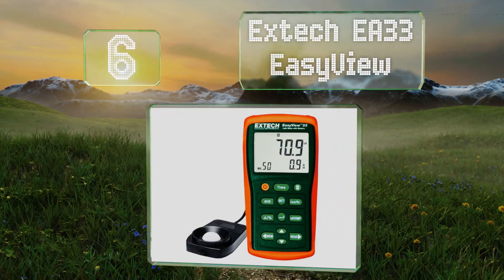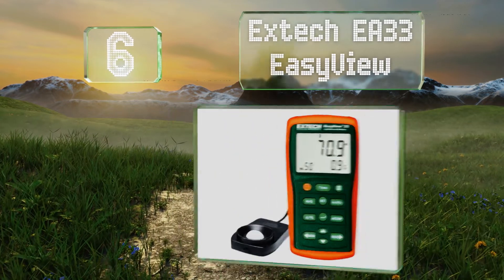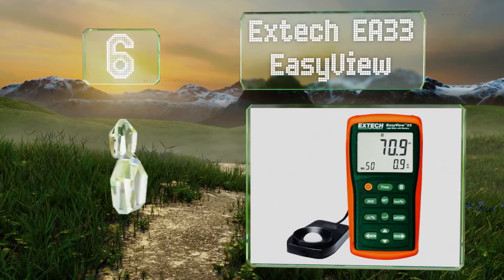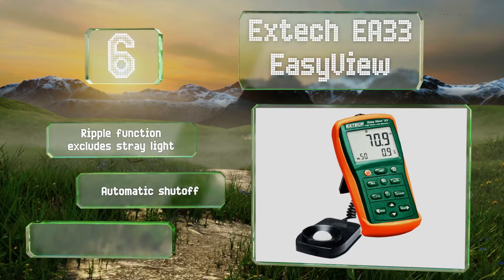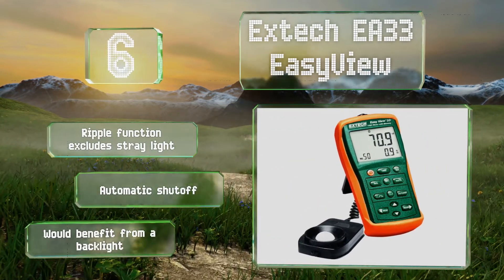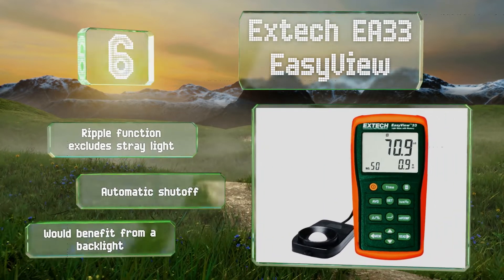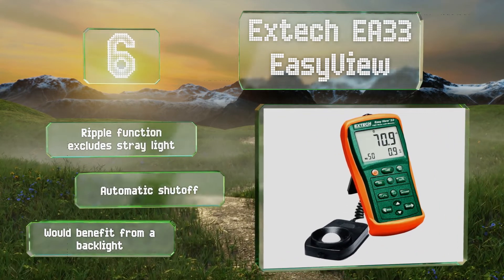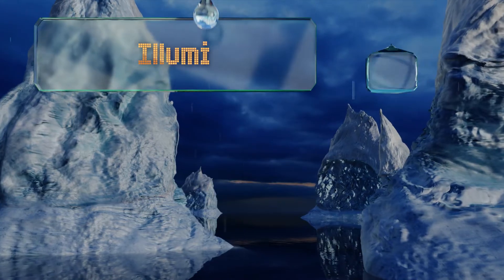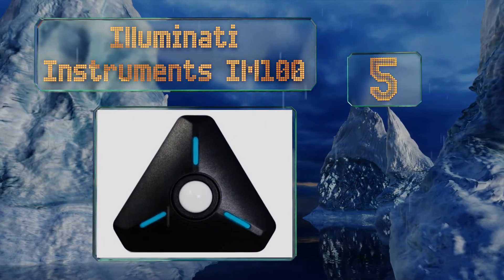Moving up our list to number six, the compact Extech EA33 Easy View features a large LCD screen and a wide measurement span reaching 99,990 foot-candles in five ranges. It can store and recall up to 50 readings, each of which is marked with a convenient time stamp. It comes with a ripple function that excludes stray light and an automatic shutoff, however it would benefit from a backlight.